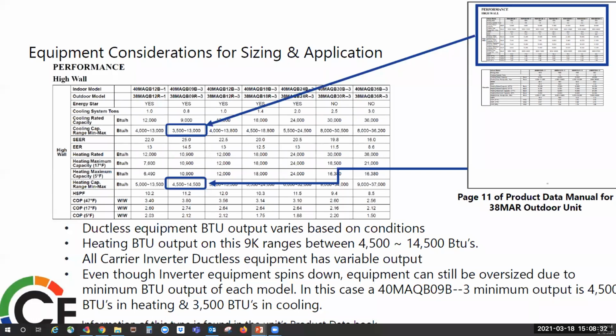Another thing to think about is that ductless units all have a minimum runtime of about 7 minutes, and this is for oil return. This can cause overheating and overcooling. Sometimes this overheating and overcooling can be adjusted in the temperature compensation settings. On multi-head units, there's also bleed-by because the EXVs do not close all the way. There are some other things that need to be taken into consideration when sizing. And just remember that these are heat pumps, most of them are air conditioners, and they do have limits.